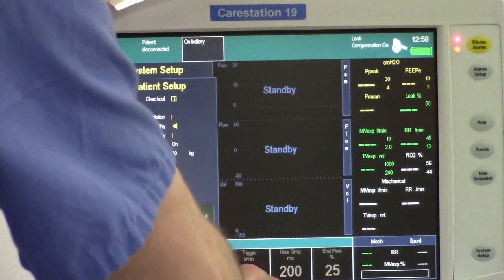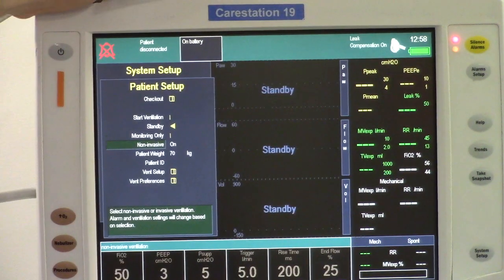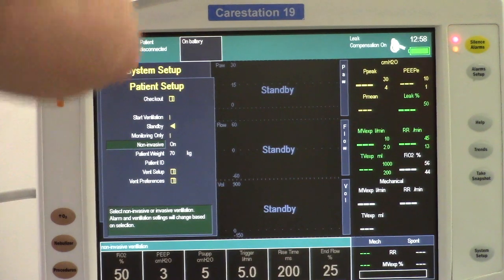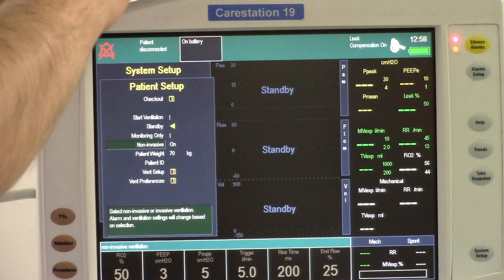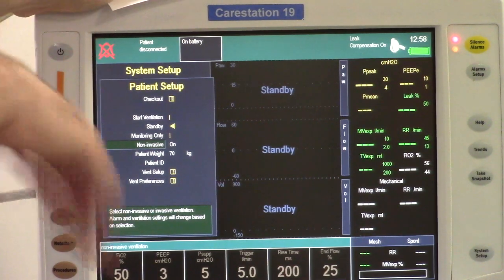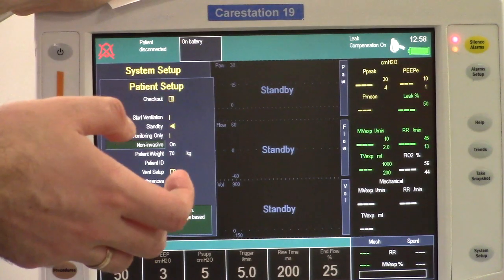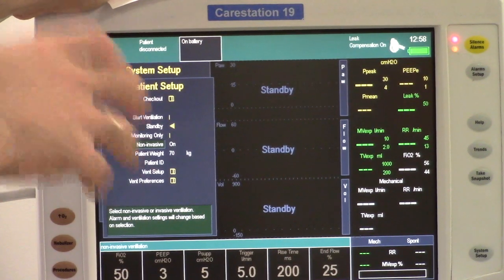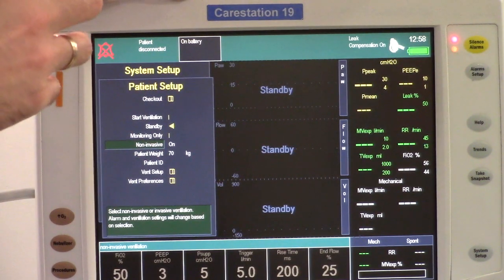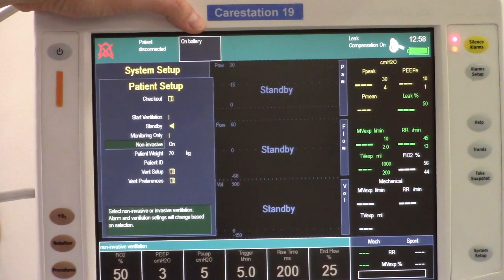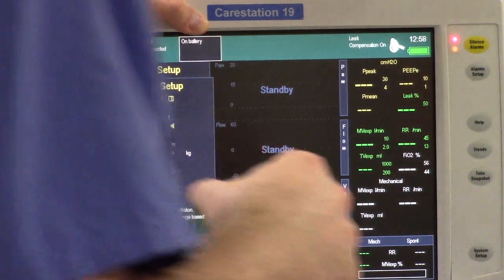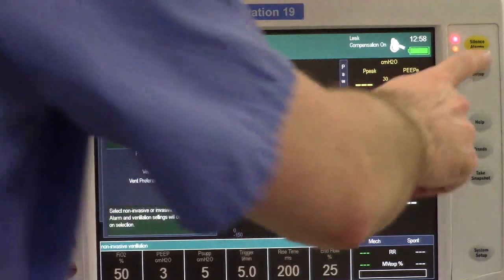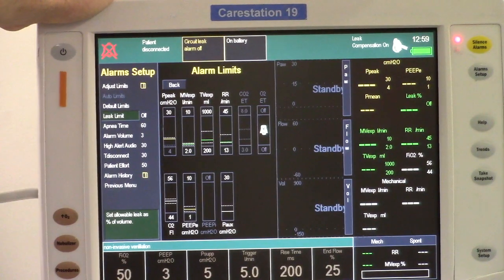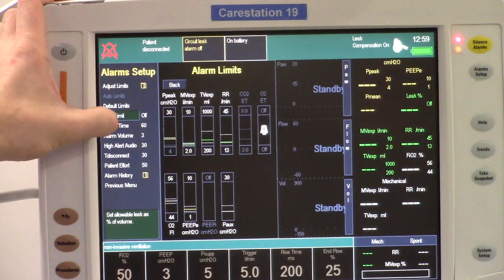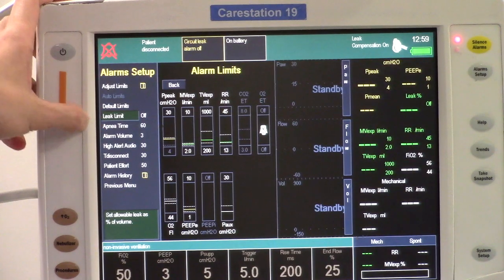Okay. You'll usually have a lot of issues with the leak with this mode, and what we recommend is just switch off the leak alarm. Because this ventilator is very sensitive, and we expect you to have a lot of leak when you're using the mask. Even if you're trying your best to fit the mask as well as possible, you'll still have some leak. That's why it's recommended even by the company to remove the alarm on leak. Even on apnea, you may change it as well if you want, but just keep an eye on it.